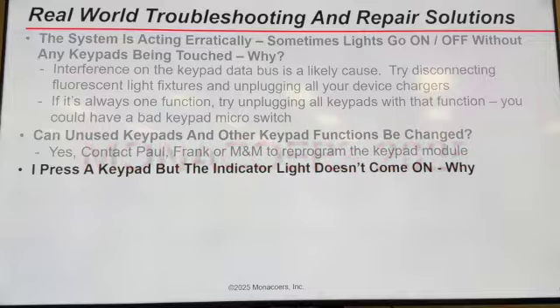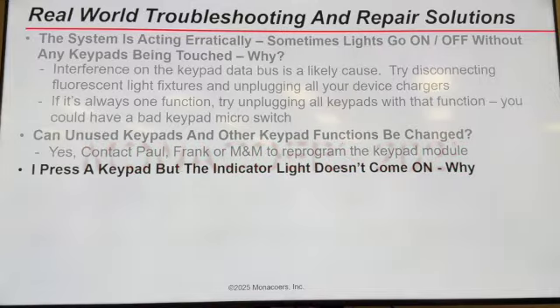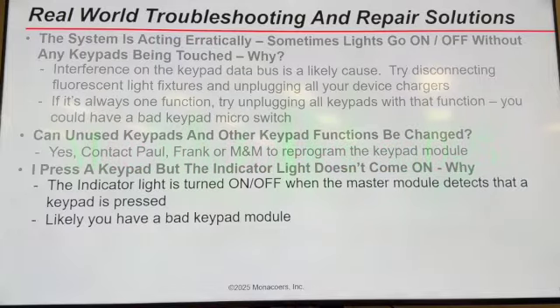I press a keypad, but the indicator doesn't come on. Why? Who knows that one? The indicator light is turned on and off when the master module detects that a keypad is being pressed, so you're assuming the master module is actually seeing that you pressed the keypad. Likely you have a bad keypad module or the button on the keypad itself. On the keypads, are there LEDs that light up and off? Yes, they are. You'll see Paul has them right there, and in a few minutes he'll demonstrate it.